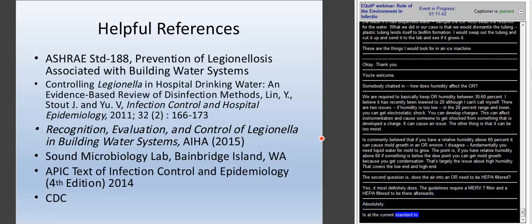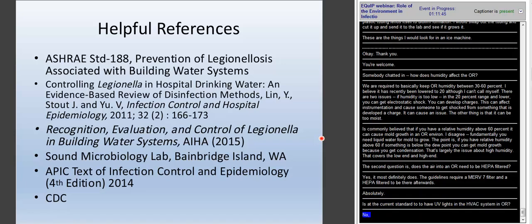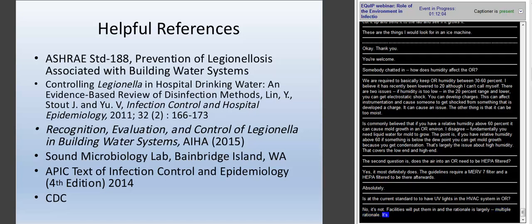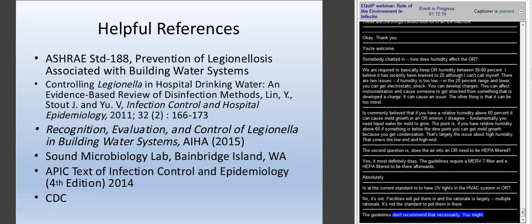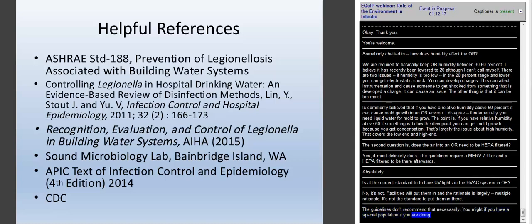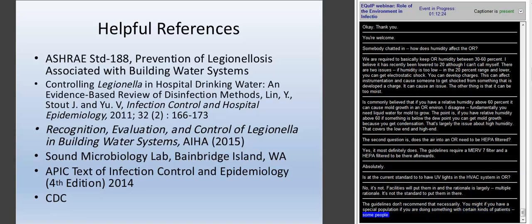Is it the current standard to have UV lights in the HVAC system in an OR? No, it is not. Facilities will put them in for various rationales. The FGI guidelines don't necessarily recommend that. You might, if you have a special population, say doing bronchoscopies on TB patients. Some people put them in the ducting to try to prevent mold growth inside the duct locations. But no, it's not the current standard to have that.